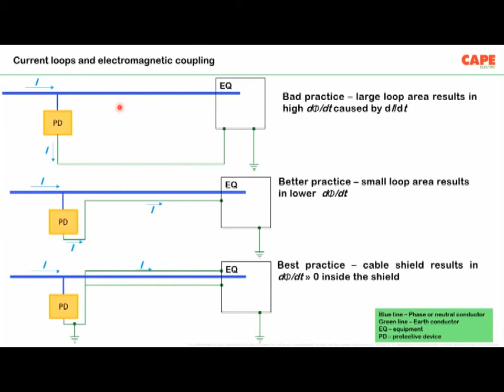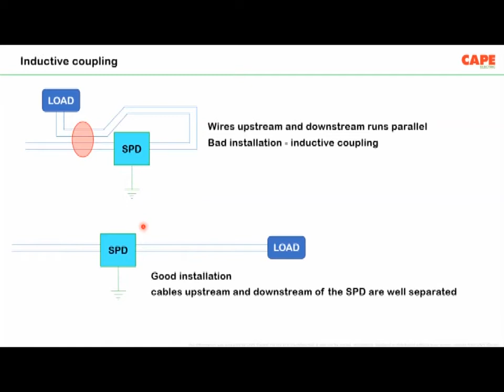If you have a large loop, as in the first picture, it may create a lot of problems, additional problems. Basically, you lose the safety. Inductive coupling. For example, there is an electrical line. You have an SPD or a filter. The outgoing of the SPD, if the wire runs parallel to the incoming, then of course your equipment will fail. There is no safety which is ensured by the SPD. So segregation of the circuits, the input circuit and the output circuit, has to be done properly so that unnecessary failures are limited.